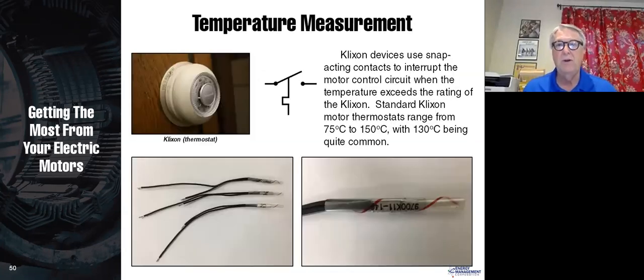Now, how can you measure temperature? Well, this is called a Klixon. It's basically a thermostat. Works just like the thermostat in your house. When it gets too hot, that little contact in there will open, and you can buy Klixon devices in many different temperature ratings, depending upon at what point you want to stop the motor. So whenever that Klixon opens, you are going to put it in the control circuit and stop the motor. And it's up to you to decide what temperature rating you get. We're going to talk about that in just a moment.